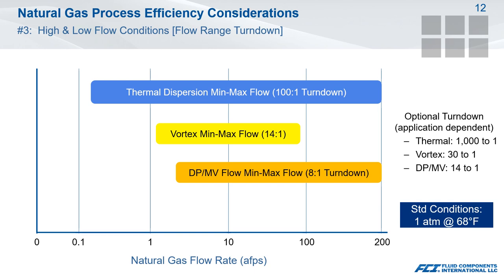Our third consideration is understanding how flow range turndown could impact our measurement. Many applications have varying demands — for example, you may see a very low flow pilot condition to keep a piece of equipment in standby mode that suddenly requires ramping up to 50% capacity or more. Properly sizing and selecting for these conditions requires clearly defined minimum and maximum flow values. As the graph illustrates, there is significant difference between the more common technologies used. The standard flow range turndown of thermal often exceeds the optional turndown capabilities of technologies such as vortex, differential pressure, and multivariable. There are also differences in the flow velocity that a given technology can measure.